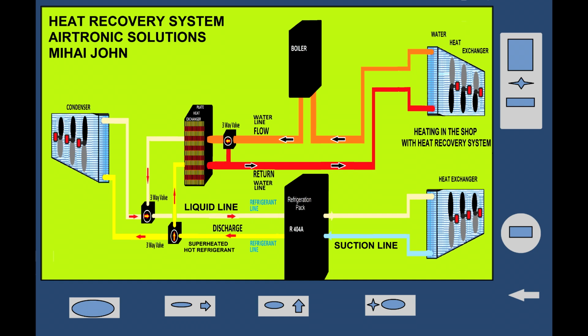Unlike in the old times, technology has advanced. Today we're using building management controls, refrigeration equipment controls, and programmable logic controls, and these controls have the capability to send data to an HMI, a human machine interface. You can call it a front end panel. And on that panel, if the design is well done, you can see the entire installation, just like you see in this picture. So you can see the entire heat recovery system.